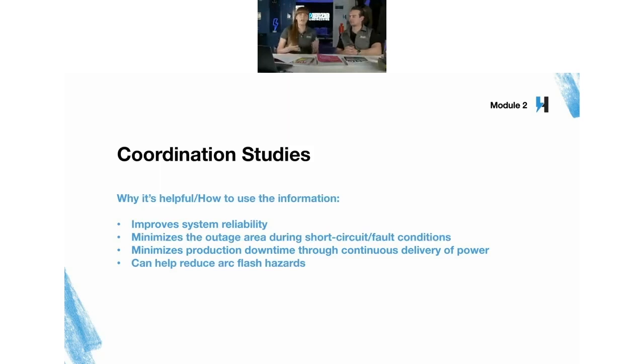So part of mitigating an arc flash hazard using engineering controls, looking at your breakers, your fuses, stuff like that, you have to be able to provide recommendations that don't affect your coordination. And also sometimes the recommendations from coordination studies result in lower arc flash hazards as well. So they do go hand in hand. So Joe, earlier you said coordination study done with arc flash, it makes sense to do that. Not everybody does though. But yes, it makes sense. Actually, you should do that.